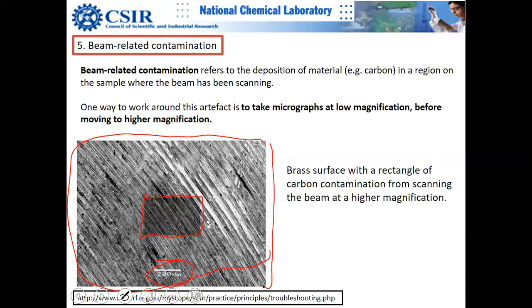go from low resolution, because in low resolution you don't damage the sample, since your current density is very small. When you start zooming, you are increasing your current density, right? Because the current is the same, but you are decreasing the area. So the damage starts happening. Obviously, you can play with other things, like decreasing the current and everything, but it's there. Most of the time, you can see that. So this is because of some organic.